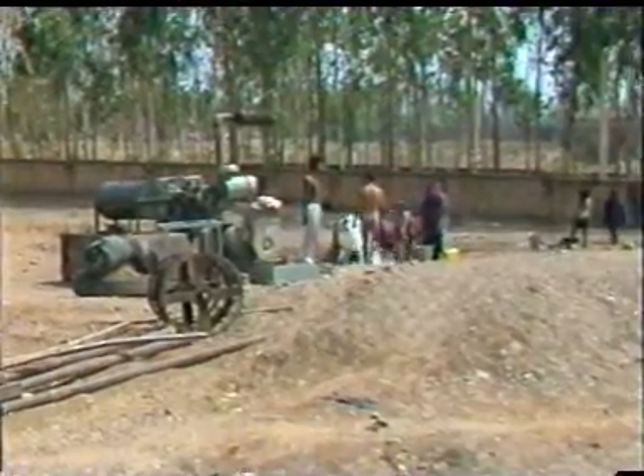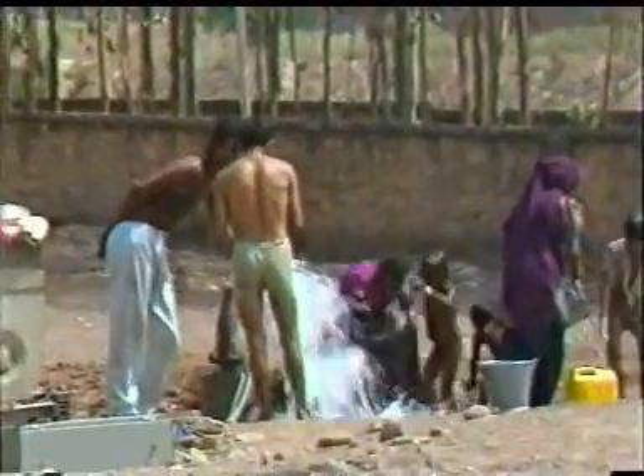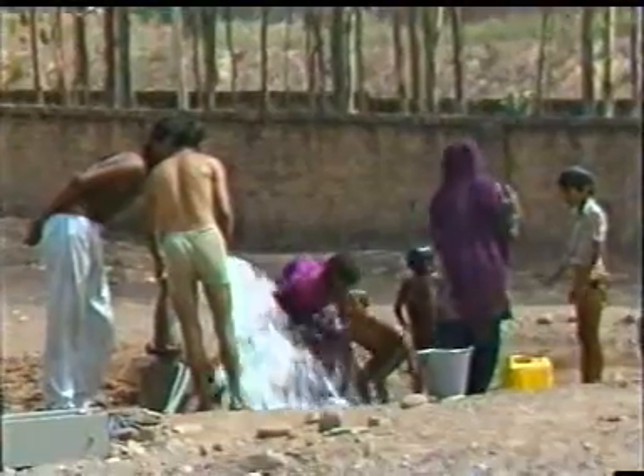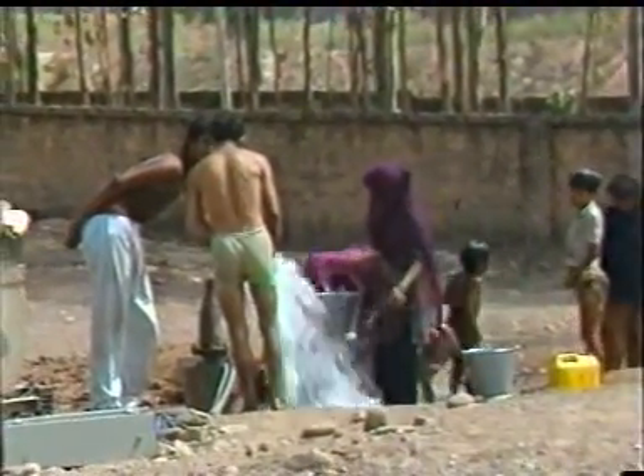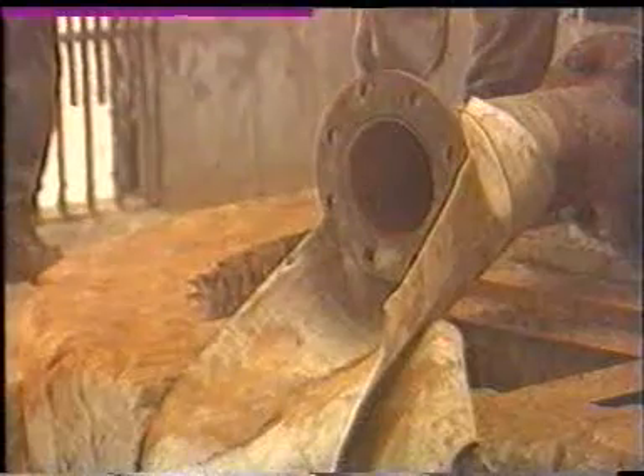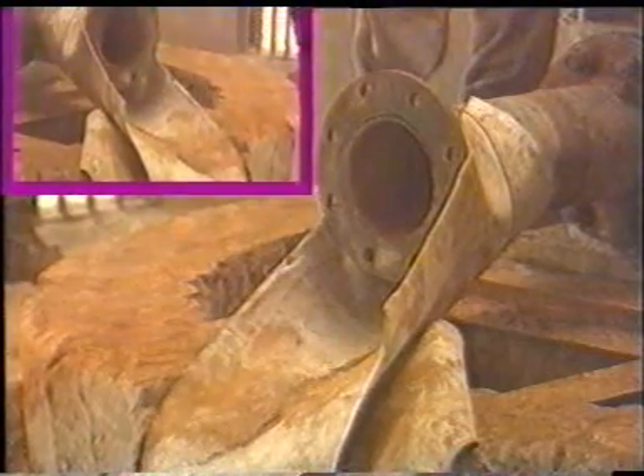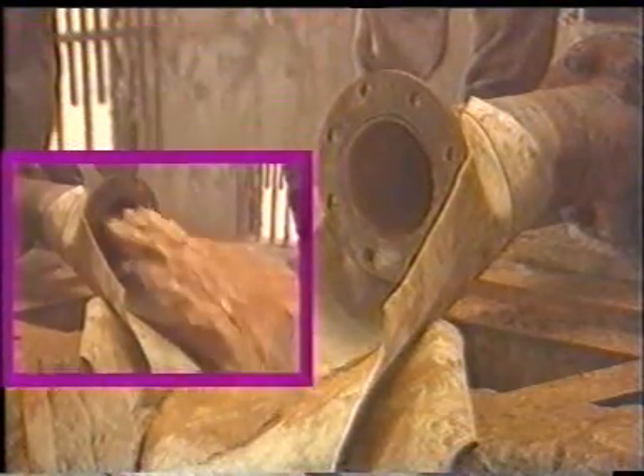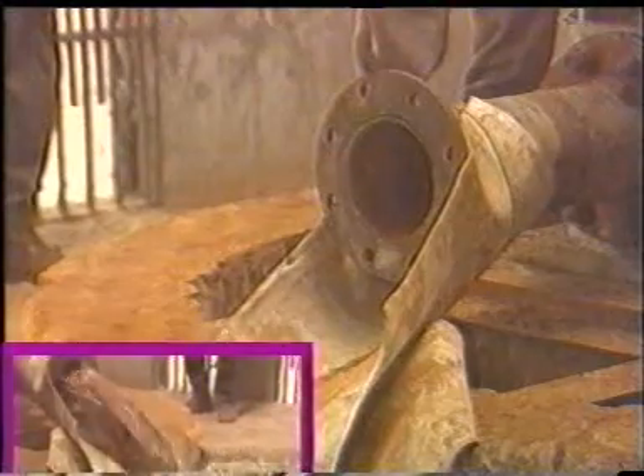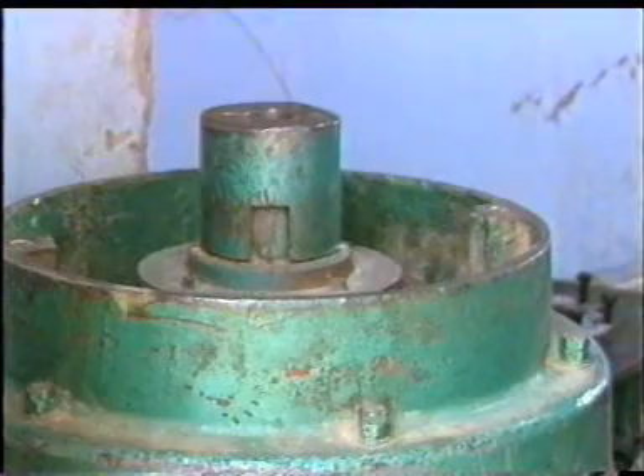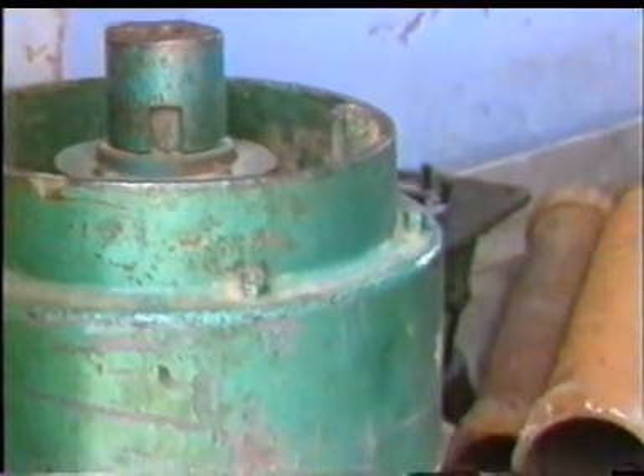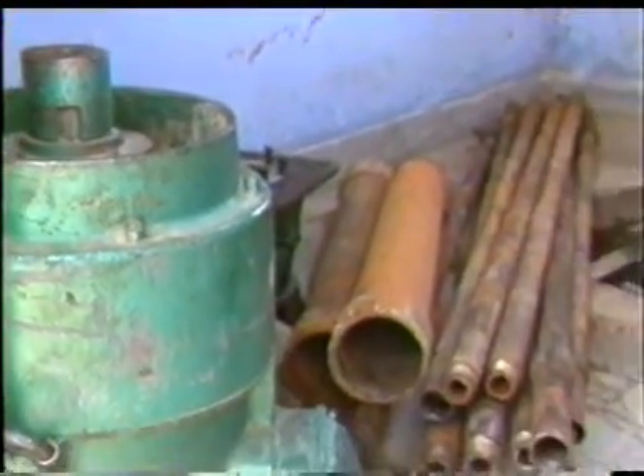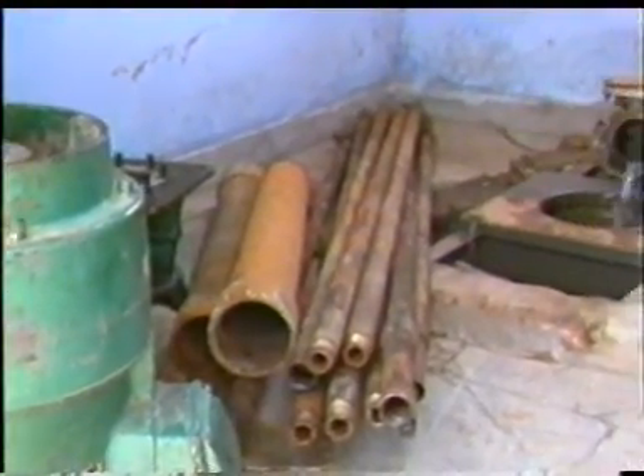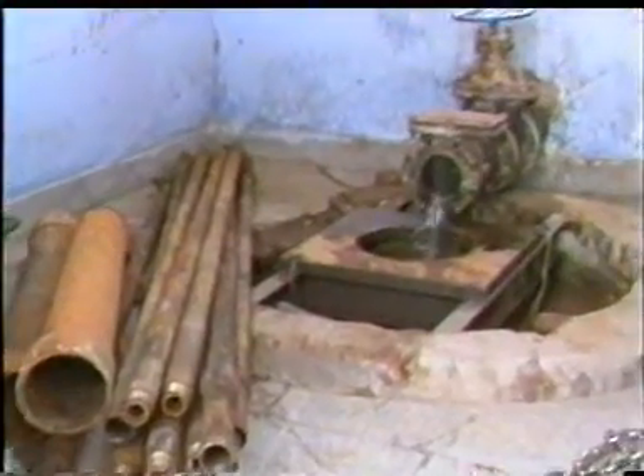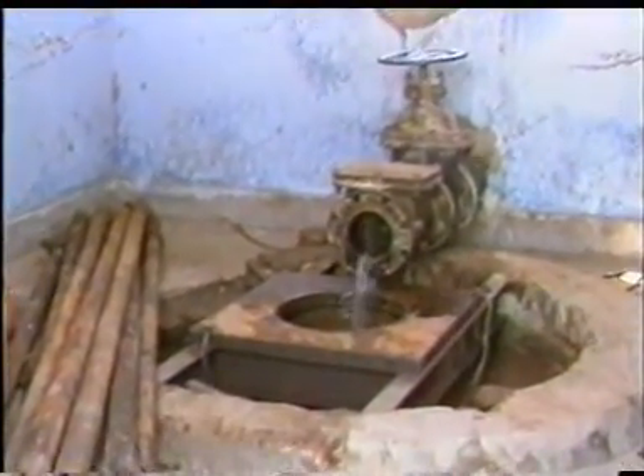Usually, wells are not subjected to periodic inspection and testing due to out of sight, out of mind attitude. Any deterioration in a well slowly develops to a critical point and then accelerates rapidly to its failure. A tube well may fail due to faults in its design, construction, operation, and maintenance.